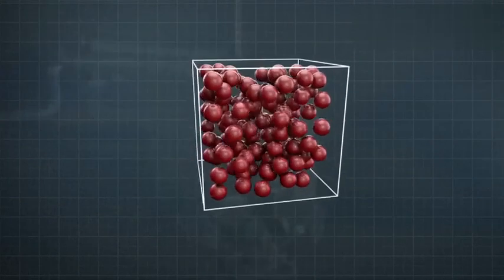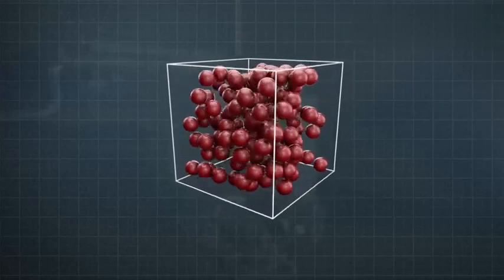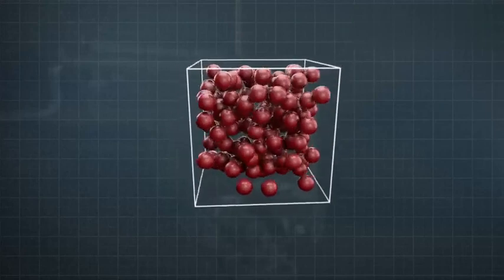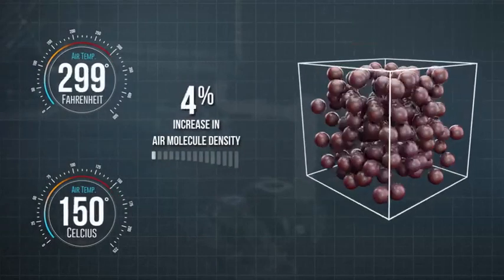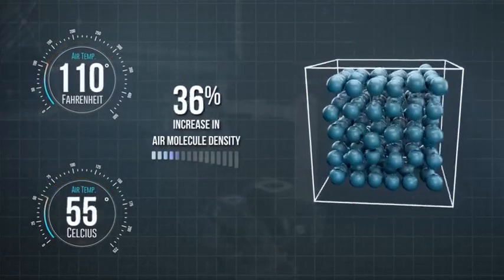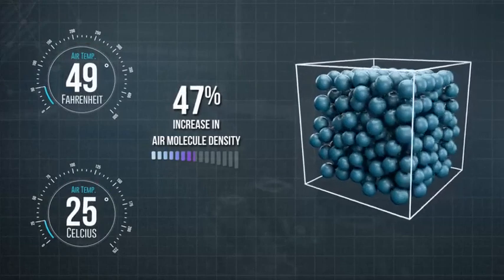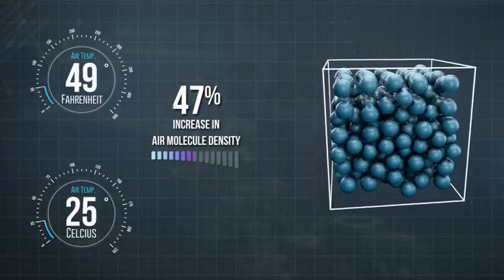It's important to cool the air before it enters the second stage, as hot air will have expanded. When cooled, the air contracts, providing a greater number of air molecules in the same volume. This results in more efficient second stage compression.